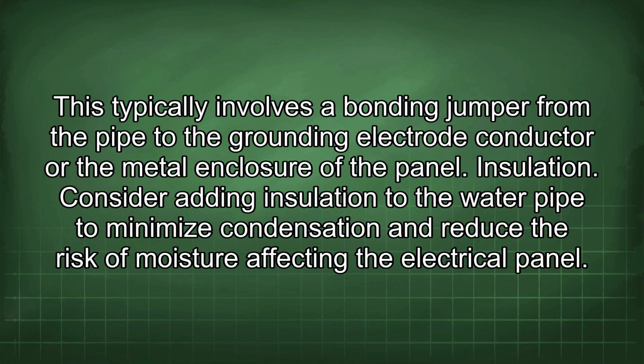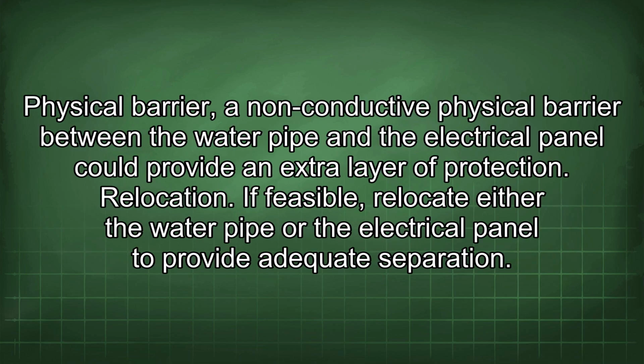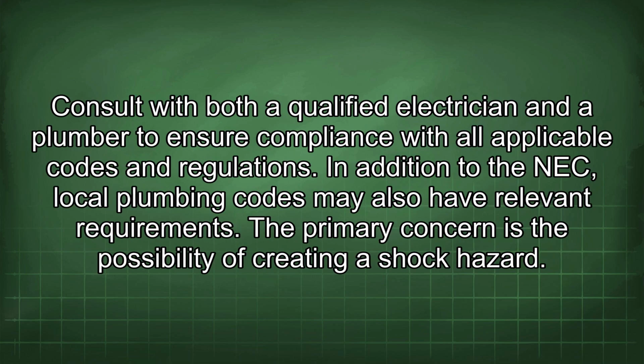Insulation: consider adding insulation to the water pipe to minimize condensation and reduce the risk of moisture affecting the electrical panel. Physical barrier: a non-conductive physical barrier between the water pipe and the electrical panel could provide an extra layer of protection. Relocation: if feasible, relocate either the water pipe or the electrical panel to provide adequate separation. Consult with both a qualified electrician and a plumber to ensure compliance with all applicable codes and regulations.